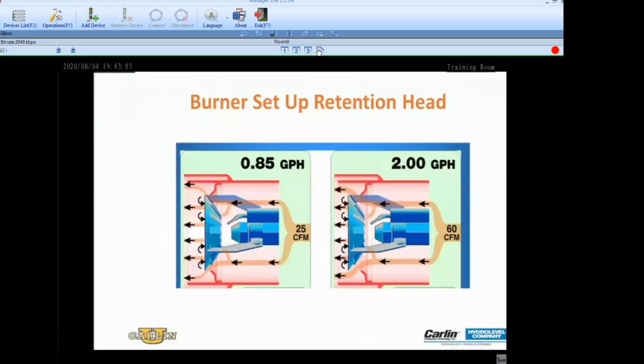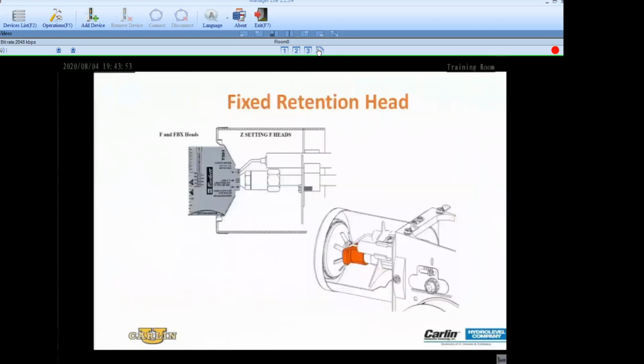The concept of flame retention, high pressure, low pressure, what causes the flame to pull back and burn tight against the head. How much air, how many CFM of air are you allowing as you roll that flame retention head up further in the air tube or pull it back? What happens when you open the air band on your burner? You're allowing more air, so is that greater static pressure in your air tube? Is that less static pressure? How is that affecting your flame retention? Too little air, too much air? Concepts that sometimes take time to explain and understand to the average tech. But once understood, it makes it that much easier to adjust a burner and understand why your burner may not be running correctly.